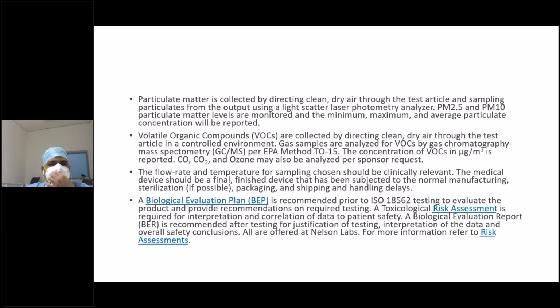The particulate matter directed through the device is collected and sampled, tested by light scattering photometry and analyzed for particulate matter of 2.5 or 10 microns. Then, depending on monitoring, the minimum, maximum, or average concentration is recorded. Volatile organic compounds are collected in the same way by directing clean dry air through the test article in an environment, and gas samples are analyzed for VOCs by gas chromatography or mass spectrometry, and the concentration of VOCs in micrograms per cubic meter is reported. Toxic gases like carbon monoxide, carbon dioxide, and ozone can also be tested.